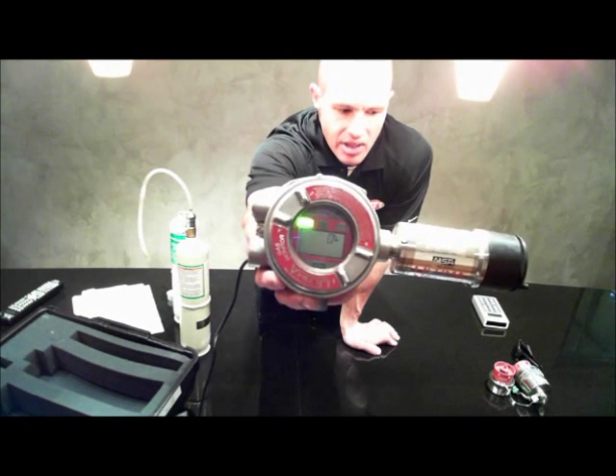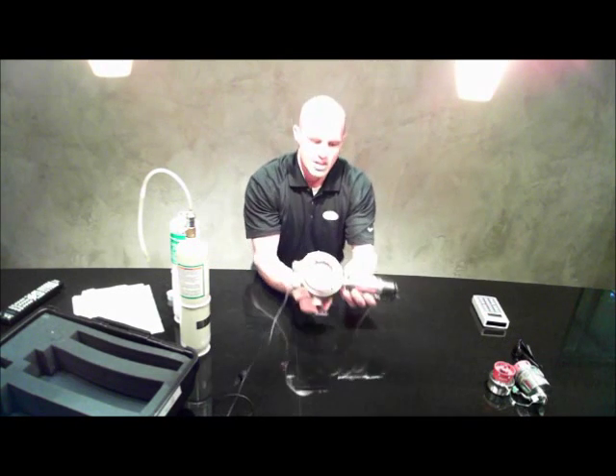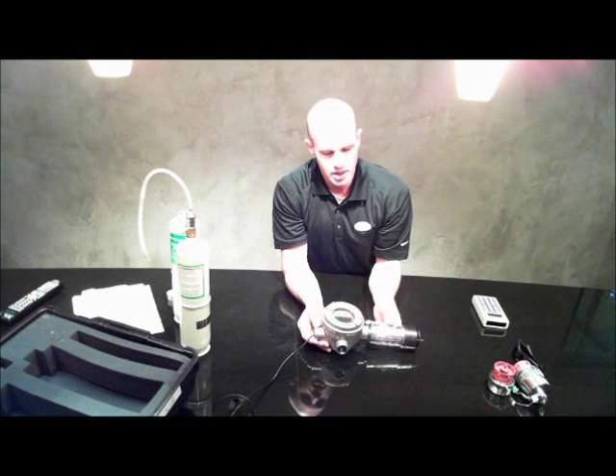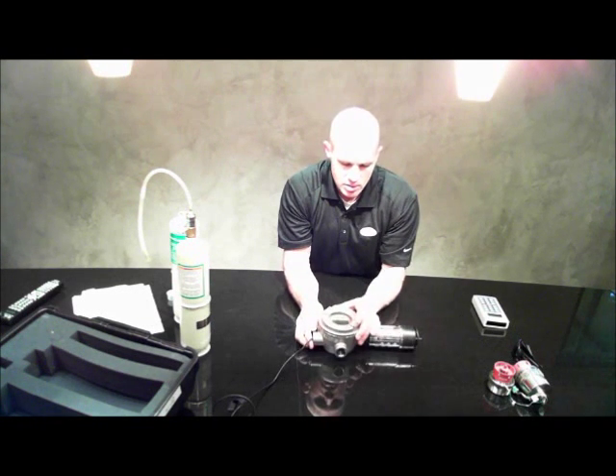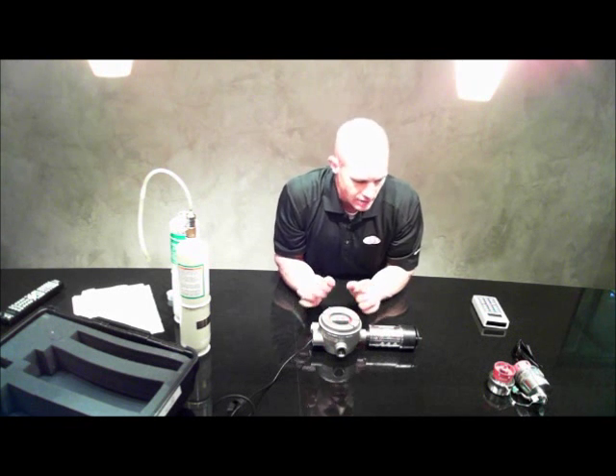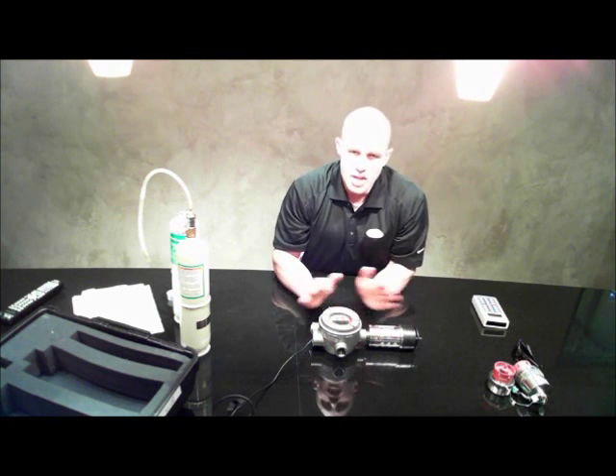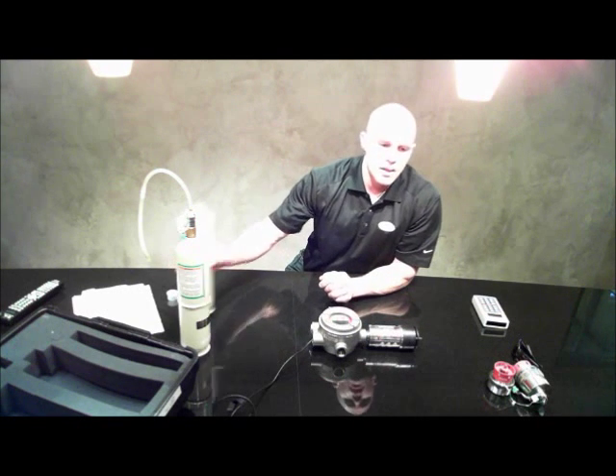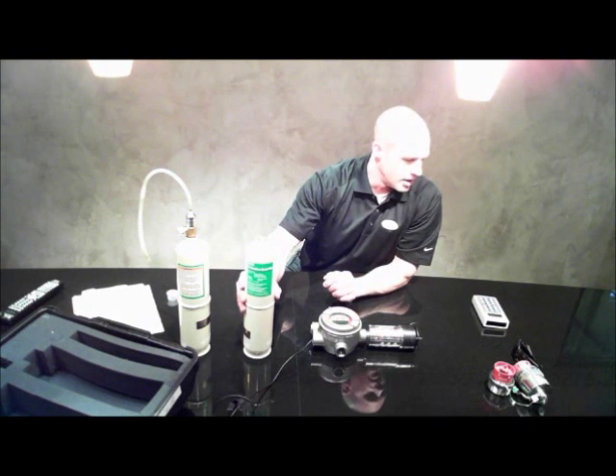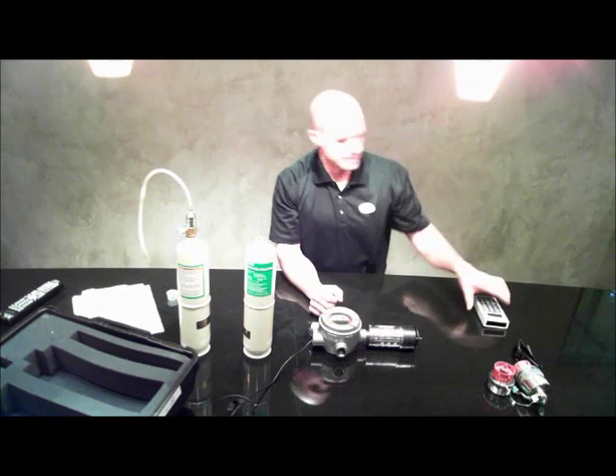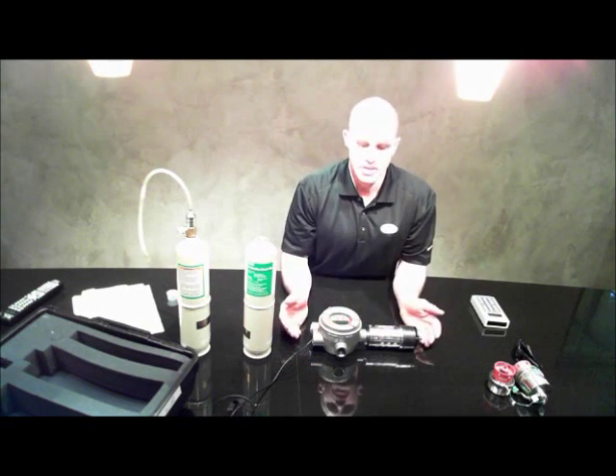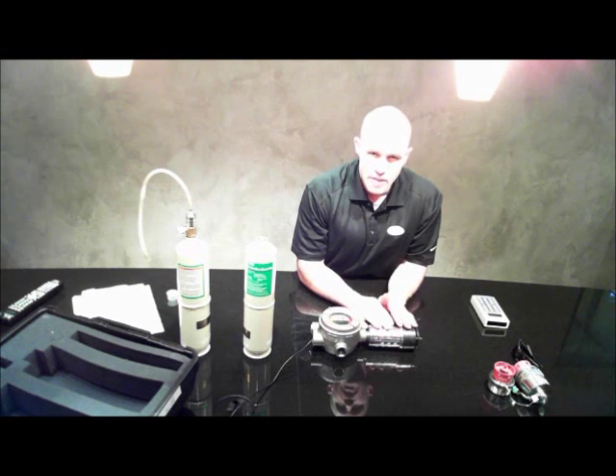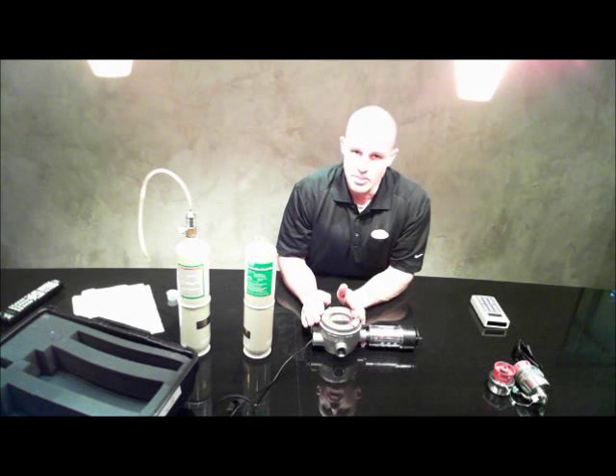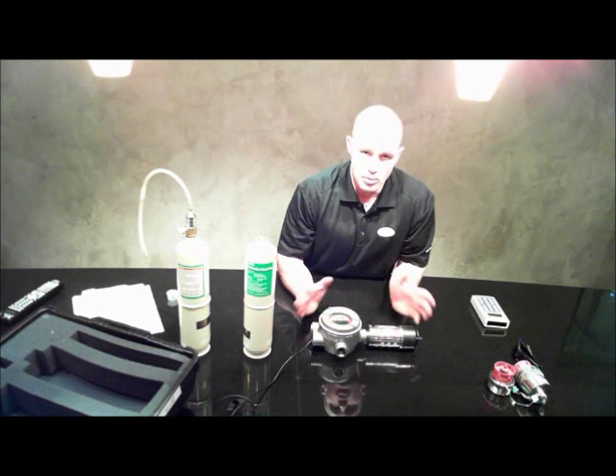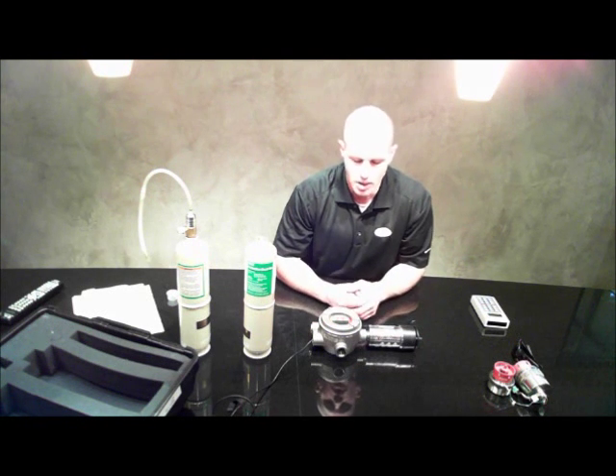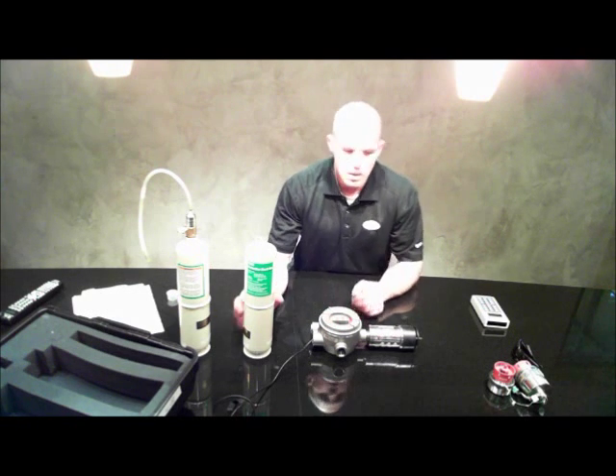So I'm hoping that you can see that. So we're back at 0. Everything's good with the sensor. Green light, normal status, everything's good, reading 0%. So that's an initial calibration. I'd like to show you a standard calibration too. What an initial calibration does is it sends all of the information that's in the sensor up into the transmitter. So that's why it's important when you first put a sensor into service to do an initial calibration.